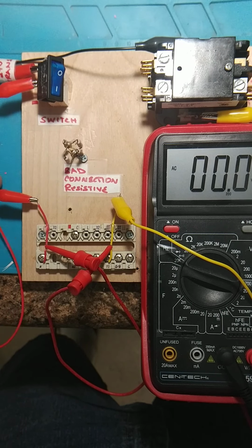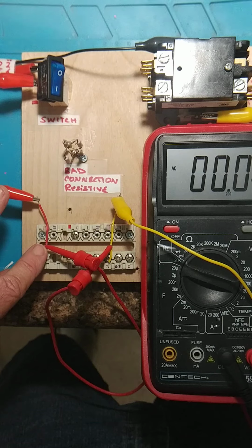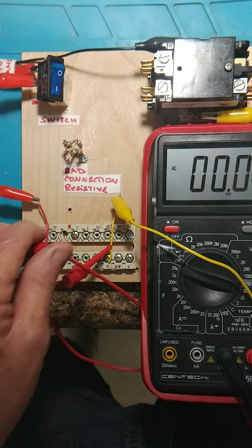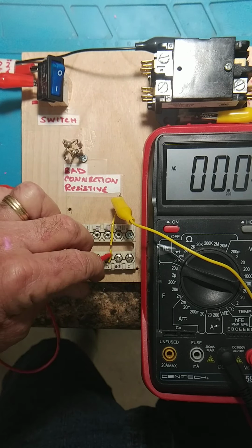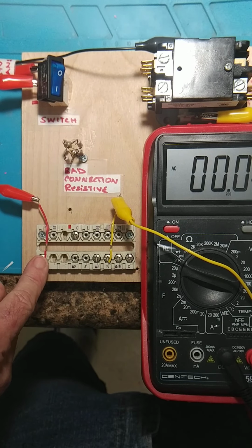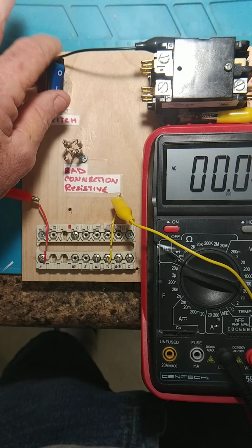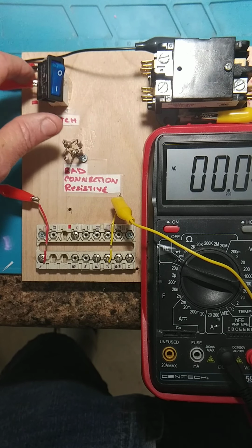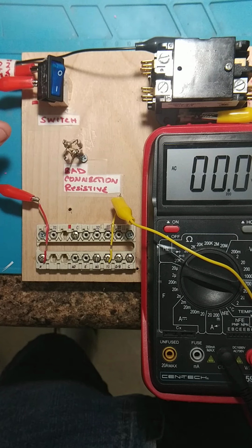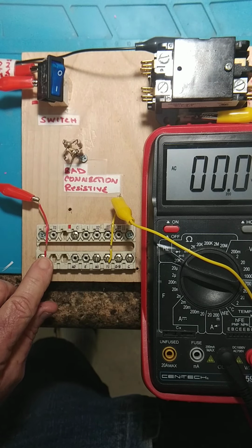I've got my 24 volts coming over and connecting to the R terminal, and I'm going to take these off. This is coming over into my R terminal. So this could be like a float switch that's breaking R from the transformer. R is in series with this switch going into R on my thermostat.